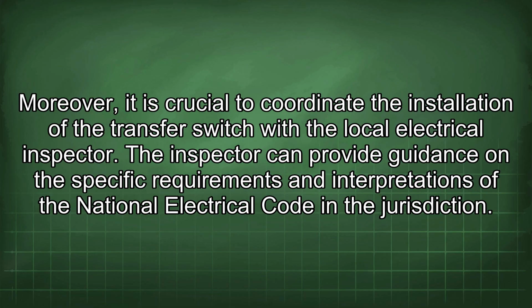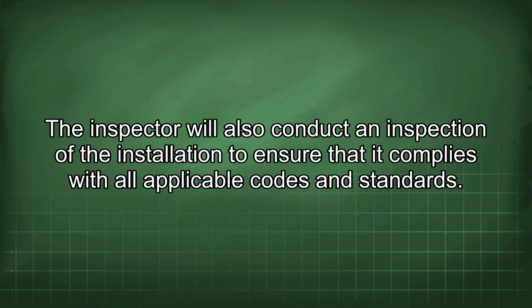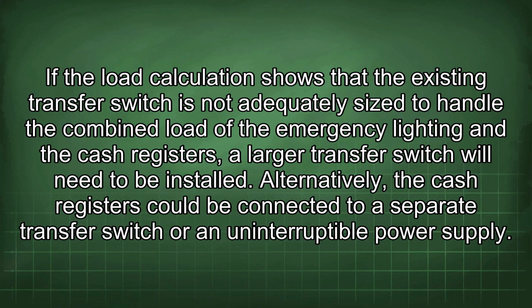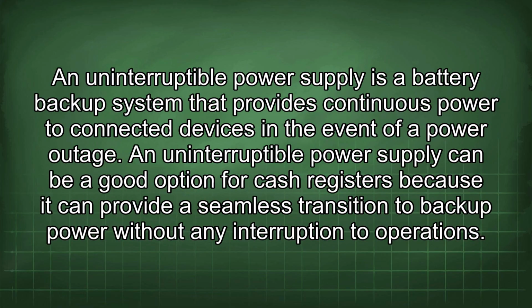Moreover, it is crucial to coordinate the installation of the transfer switch with the local electrical inspector. The inspector can provide guidance on the specific requirements and interpretations of the National Electrical Code in the jurisdiction. The inspector will also conduct an inspection of the installation to ensure that it complies with all applicable codes and standards. If the load calculation shows that the existing transfer switch is not adequately sized to handle the combined load of the emergency lighting and the cash registers, a larger transfer switch will need to be installed. Alternatively, the cash registers could be connected to a separate transfer switch or an uninterruptible power supply. An uninterruptible power supply is a battery backup system that provides continuous power to connected devices in the event of a power outage.